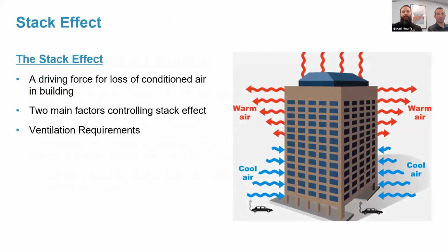This ultimately feeds into the stack effect, where cool air will tend to sink towards the bottom of the facility, and the warm air naturally stratifies and goes towards the roof or the top levels of the building. In a high-rise example like this, it would be important to maintain proper ventilation so that the conditioned air is moving to where it needs to be throughout the building.